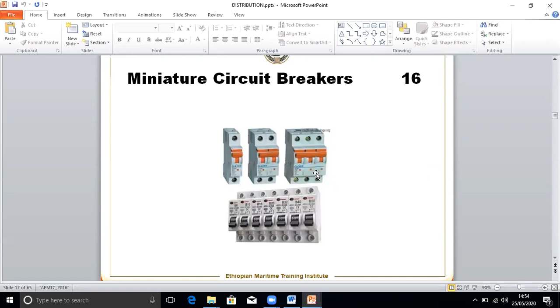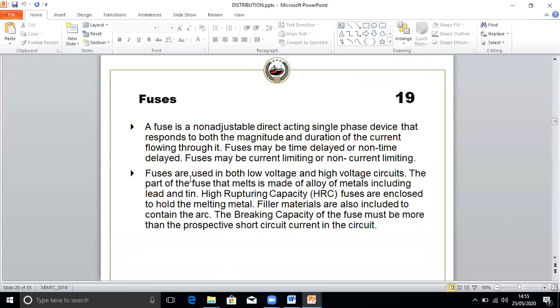Let's come to the fuse. A fuse is a non-adjustable direct acting single phase device. It responds to both magnitude and duration of the current flowing through it. A fuse may be time delayed or non-time delayed. Fuses may be current limiting or non-current limiting. And it is used for both low and high voltages.